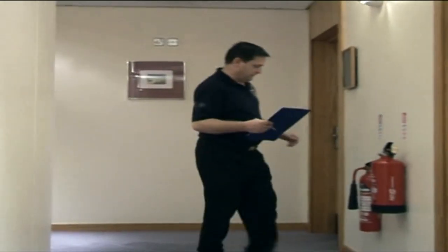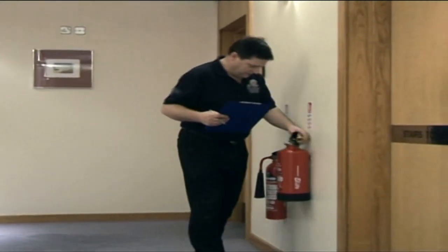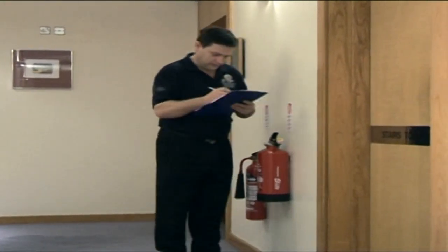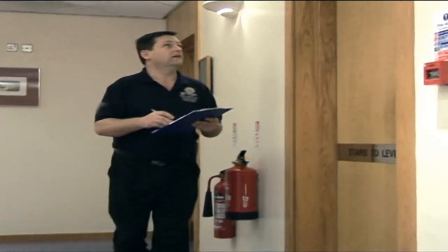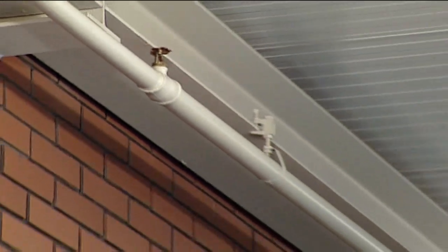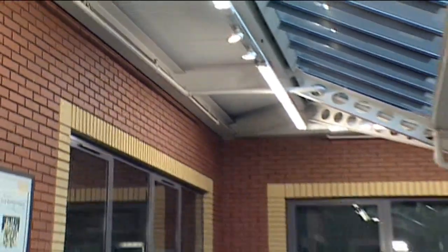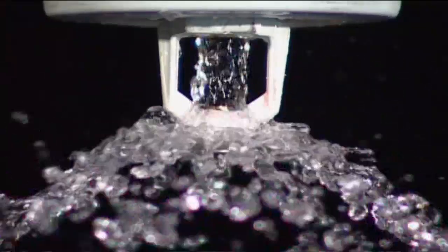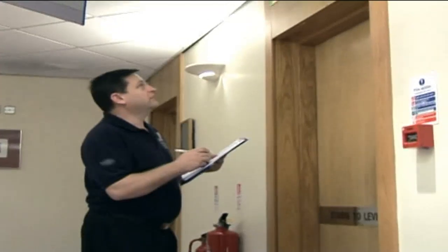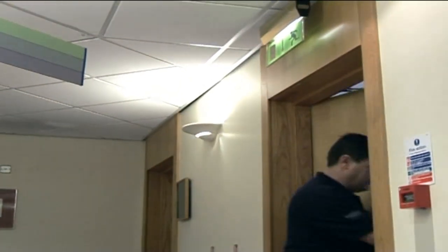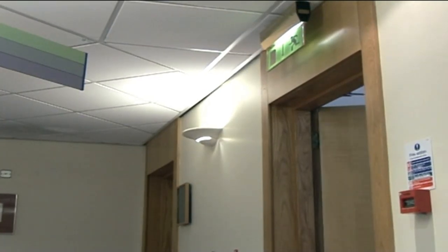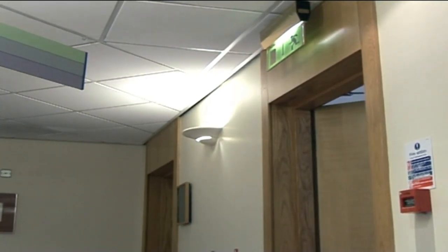A suitable number of appropriate fire extinguishers should be in place, principally in case they are needed to assist people to escape. An increasing number of schools have sprinkler systems which automatically release water to control a fire. Sprinklers are a reliable and safe way to tackle fires, helping to save lives, save money, and minimize the disruption from fire. All fire exit routes should be clearly signed. Automatic emergency lighting that operates if the power fails should illuminate signs, escape routes, and fire exits.